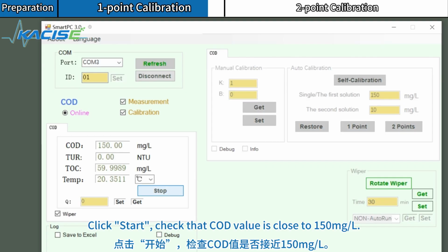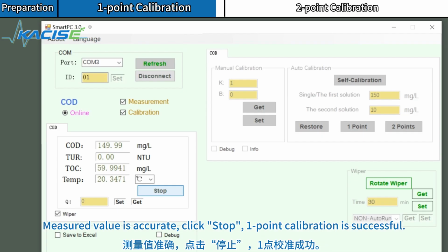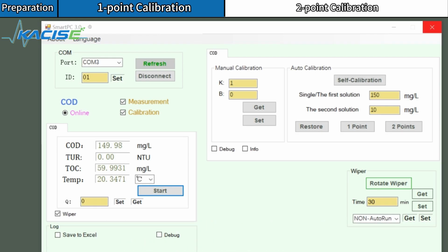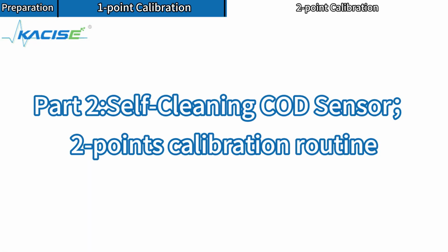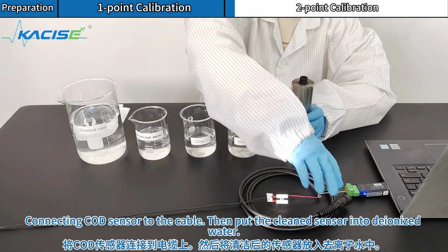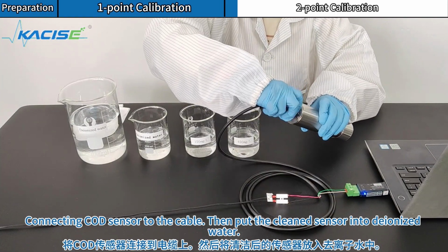Click Start. Check that COD value is close to 150 milligrams L. Measured value is accurate. Click Stop. 1-point calibration is successful. Part 2. Self-cleaning COD sensor. 2 points calibration routine. Connecting COD sensor to the cable.